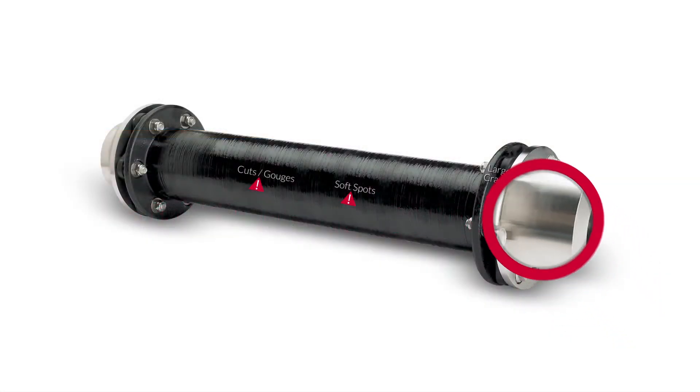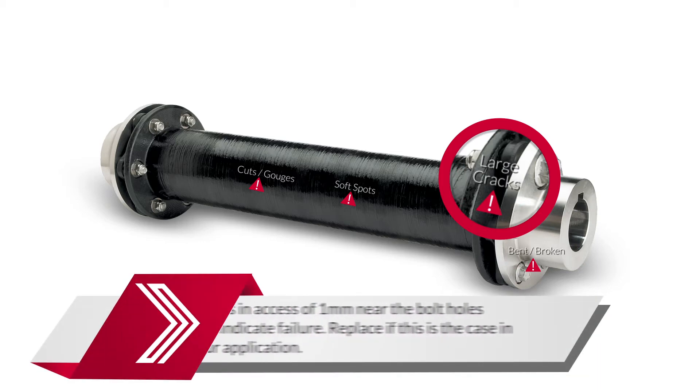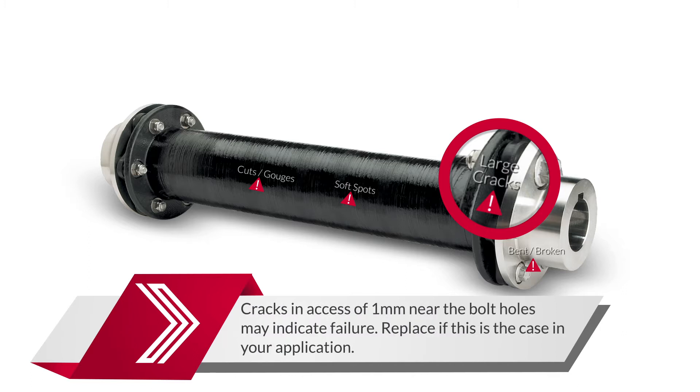The flex elements should be inspected to ensure that there are no surface protrusions or bumps, severe buckling, or large cracks. Cracks in excess of 1 mm near the bolt holes may indicate failure.